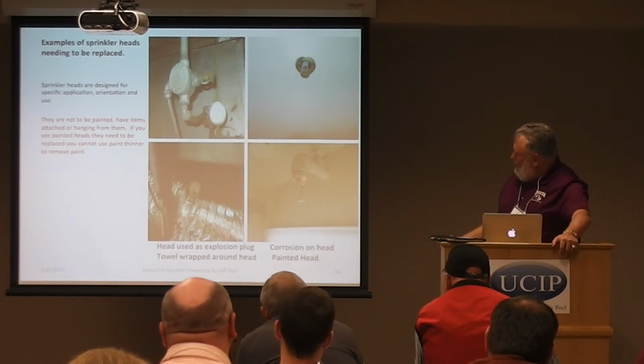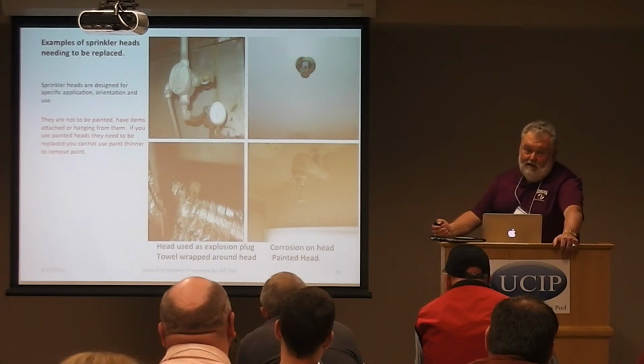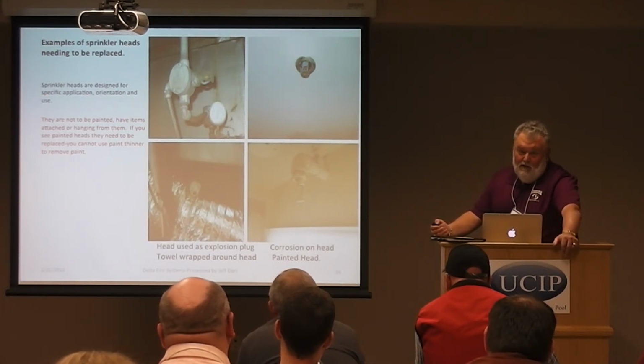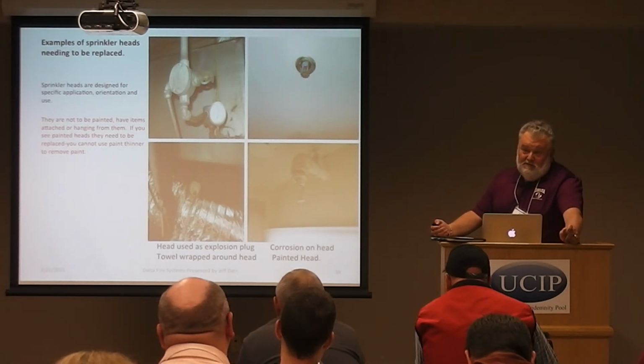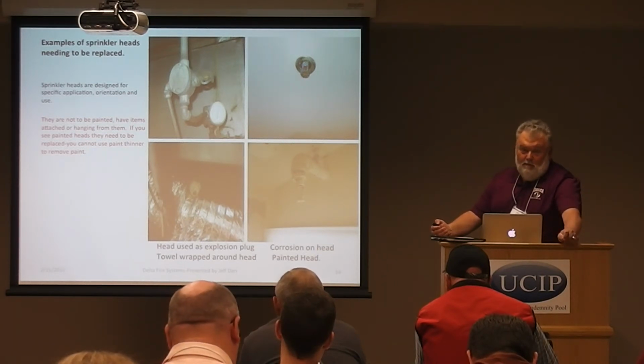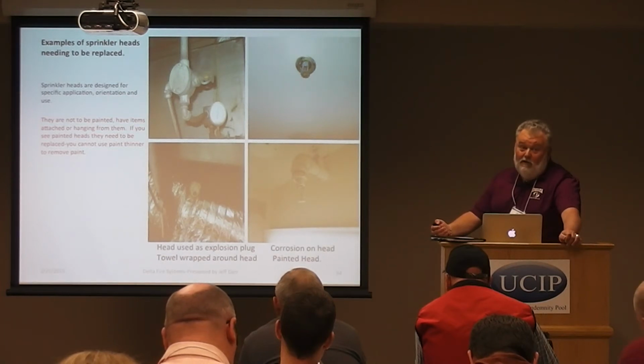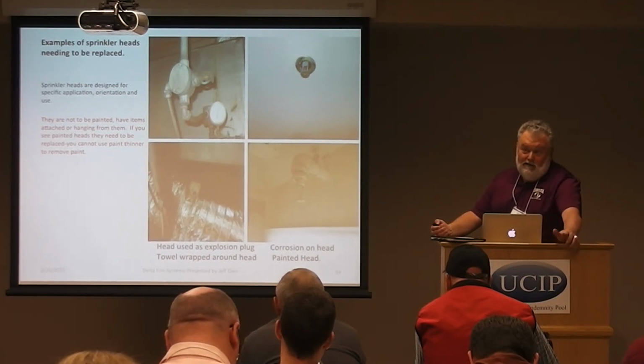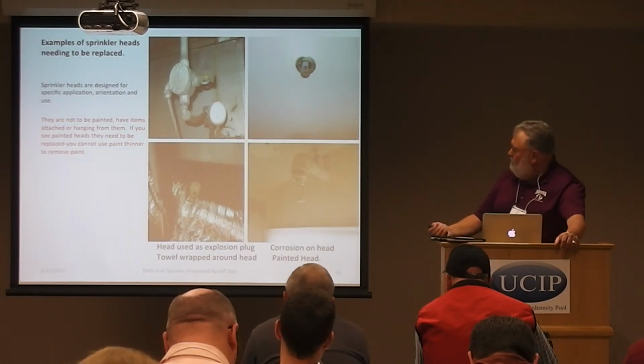This one here, that head has been painted. And code very specifically says painted heads have to be replaced. Reason being, these heads are designed to go off at specific temperatures. If you put paint on those, that's another insulation layer that would impede that head. It may never go off, or it would not operate in the time that it's supposed to and have a larger fire.